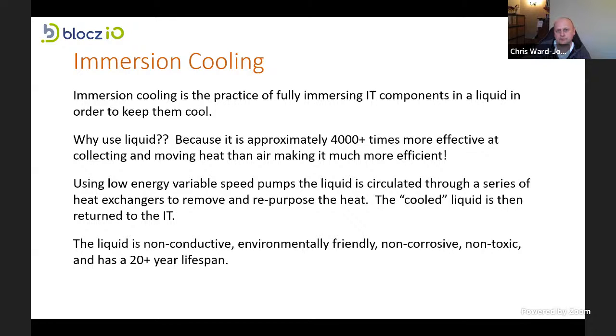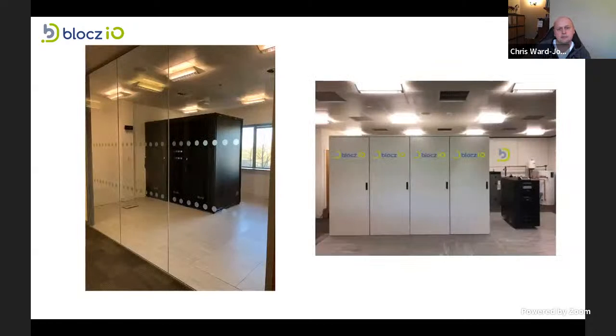So what is it? This is our building in Cambridge, where we have some racks in a data center. I say data center, this is actually a room we built as an MMR MEV room where some of the connectivity comes into the building, but it's where we used to benchmark the kit we were going to test with. This is a standard air-cooled room, no more efficient than any other data center facility - well, I suppose slightly more efficient because it's a smaller room. It's not for customer kit. These are standard data center racks, vented, with cold air pushed into the room and hot air extracted.